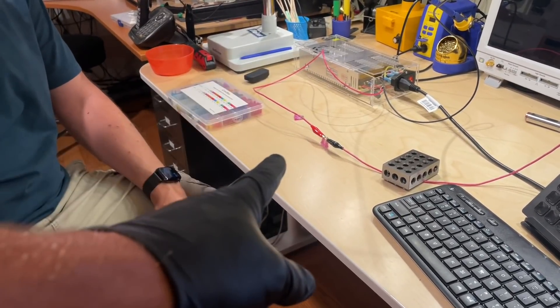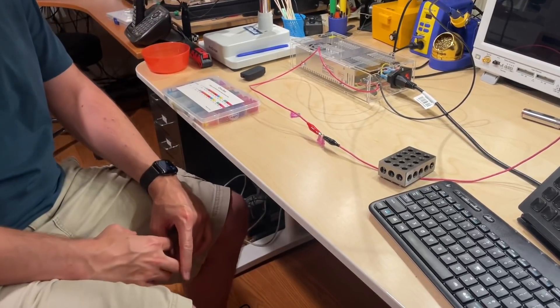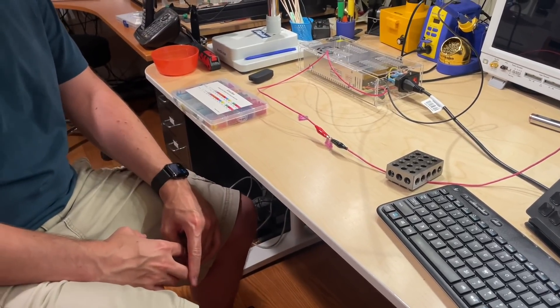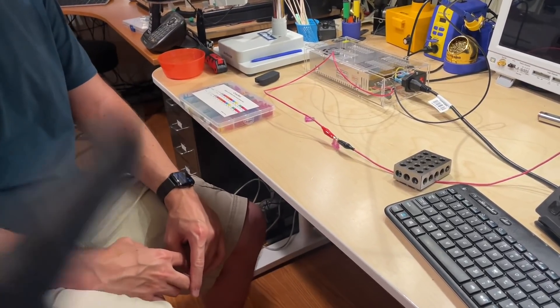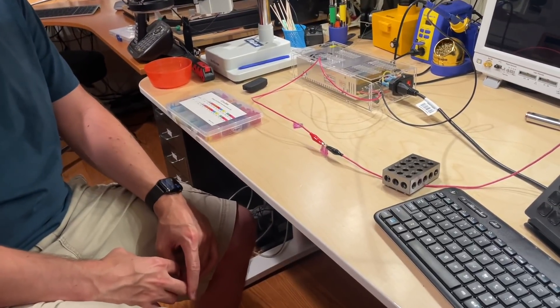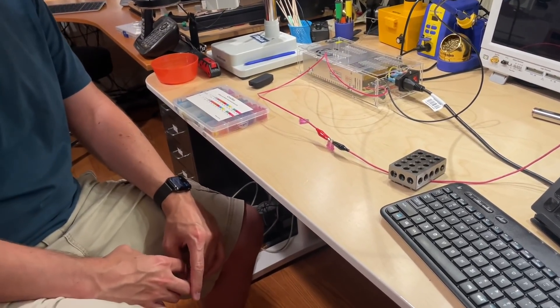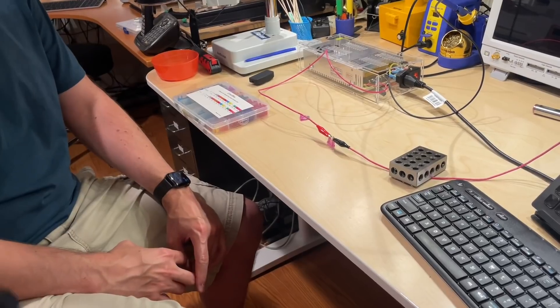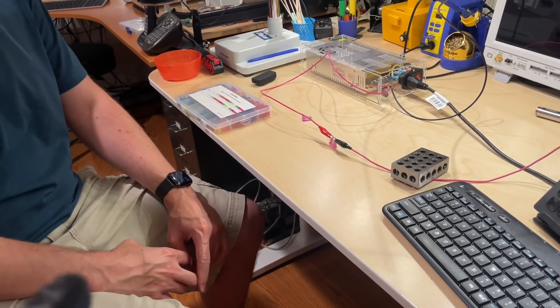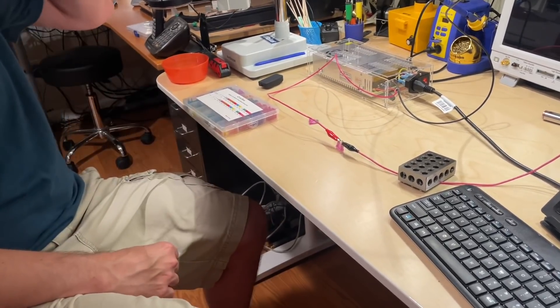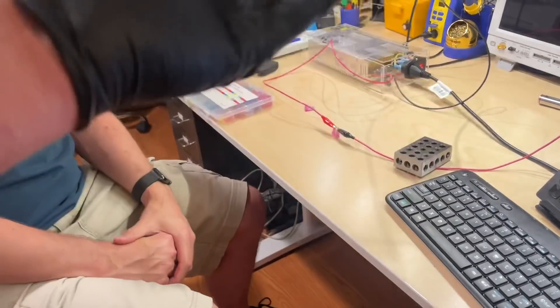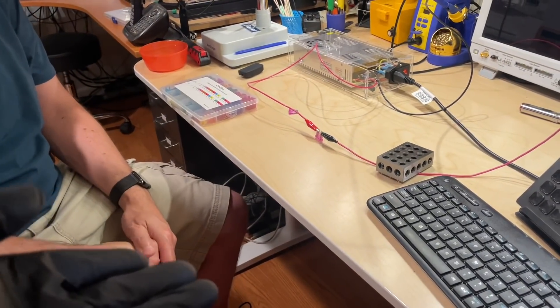In three recent cases I can think of, I have my three amp fuses which obviously are not fast acting, and in those three cases the transformer actually blew. I even used little poppers before. The one I had melted right before it actually popped. That's why I didn't trust it - kind of like a Chinese fuse. I'd rather go through a series of fast acting Bussmann fuses now.